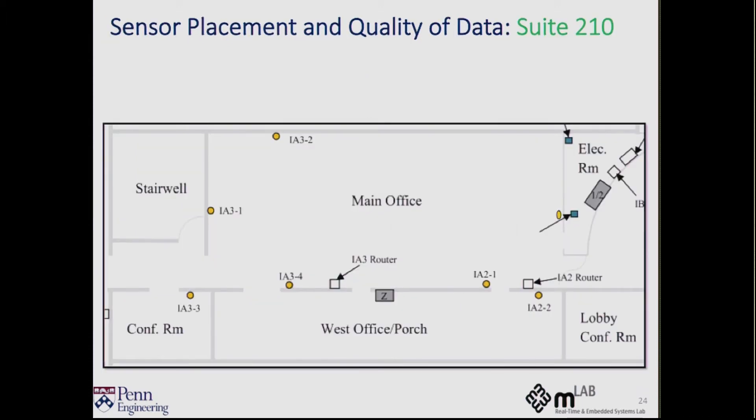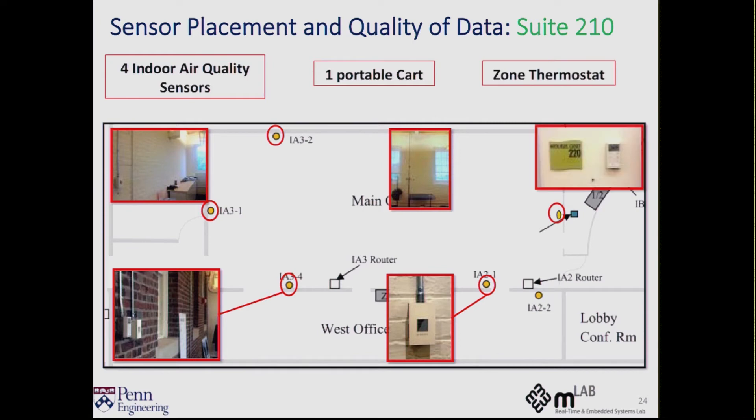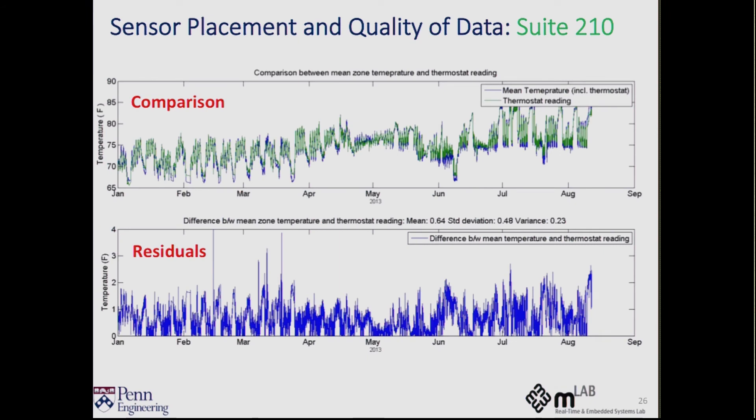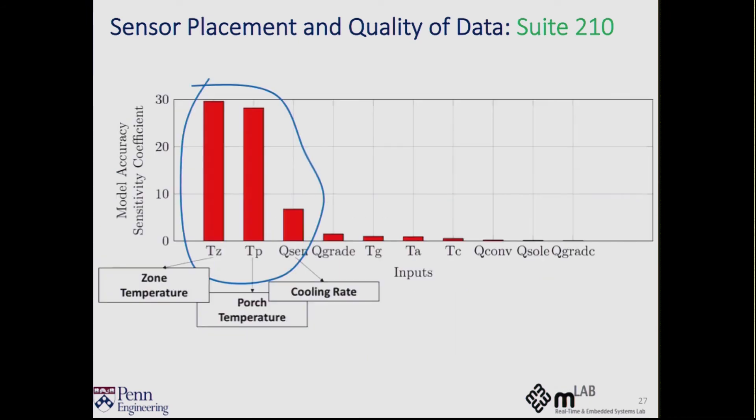So the last thing we did was to address sensor placement and how it can introduce biases in the measurement. So for one of these zones, we had a bunch of sensors which were uniformly distributed in the zone, but were measuring the same thing, the temperature of the zone. And our goal was to see if the thermostat, which is located on the south wall, has any bias in it. So we compared the mean temperature against the thermostat. And what we see is that even though there's a small bias, the zone temperature is actually the most significant or the most sensitive measurement. So even that small bias or uncertainty due to the location of the thermostat can throw off the model accuracy.